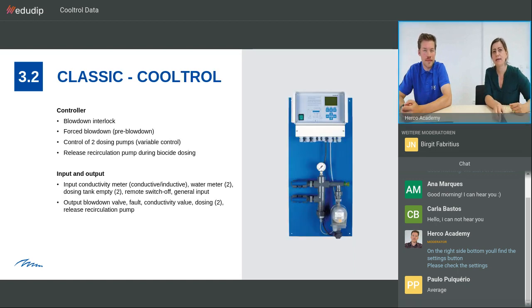Now, the next one is our classical Cooltrol controller. This has the blowdown interlock. It has a forced blowdown or pre-blowdown, which is a blowdown done before dosing of biocide, because some biocides, depending on the type of biocide, can increase the conductivity quite a bit because of the concentration of, let's say, active substances. What's a blowdown interlock?